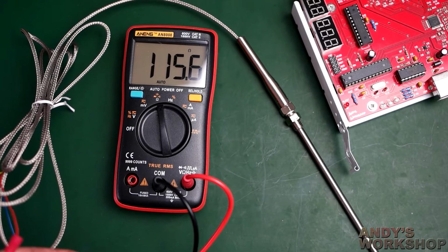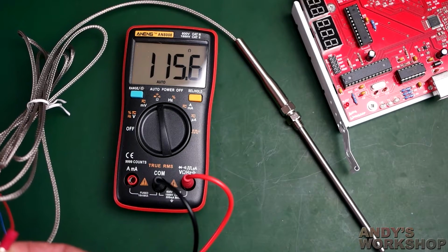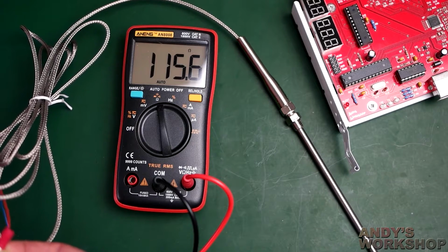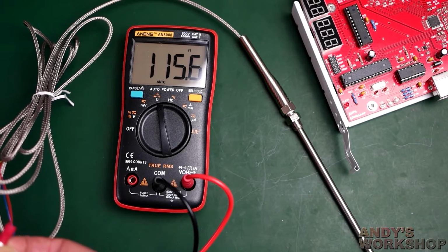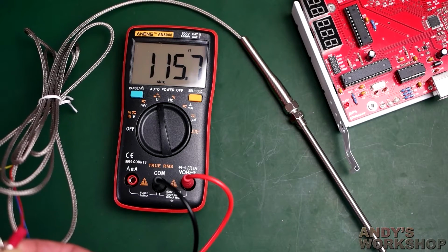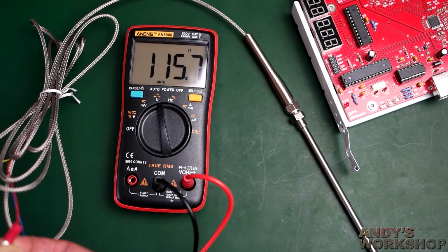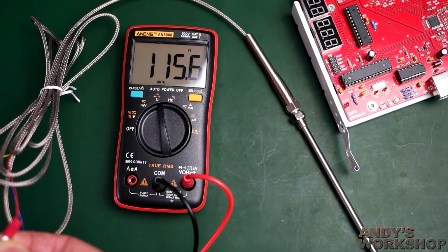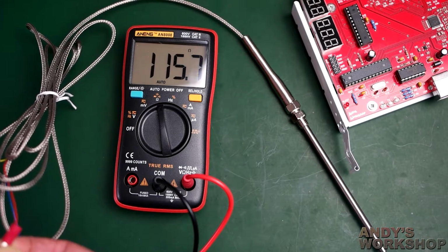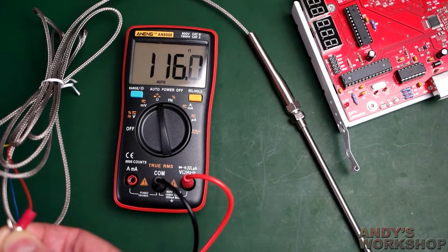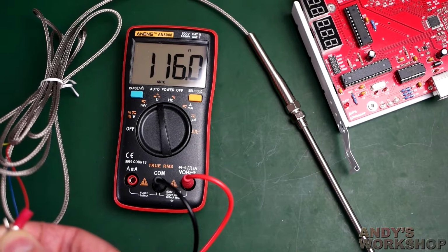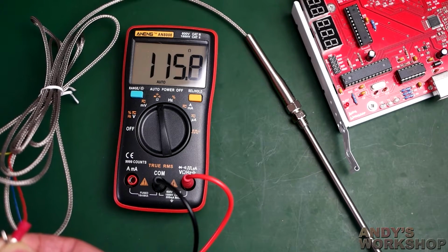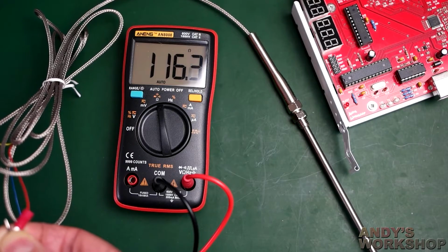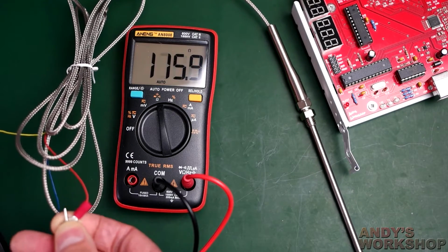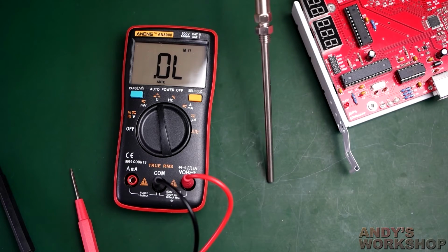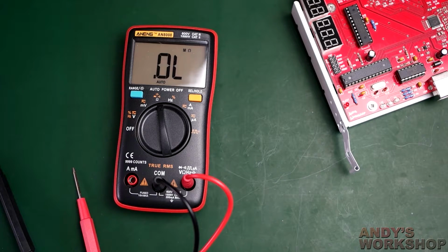My worry, of course, is that it's not a PT100. It could be goodness knows what embedded in the end of that probe. Now, obviously, the good news is that a constant offset like this can be calibrated out. That's no problem. I can do that. What I worry about is the linearity of it, and given how far off it is from nominal, whether it will actually track the changes in temperature versus resistance as a PT100 should. Basically it's a worry. So I don't think I'll be using this as my first choice probe, not by a long shot.